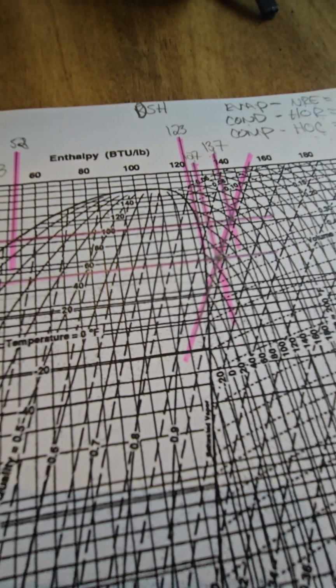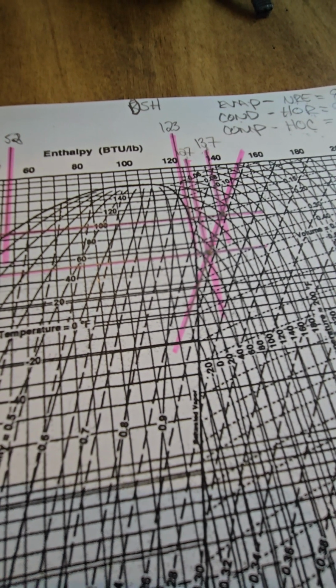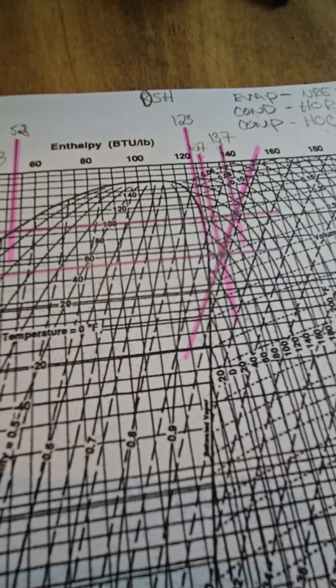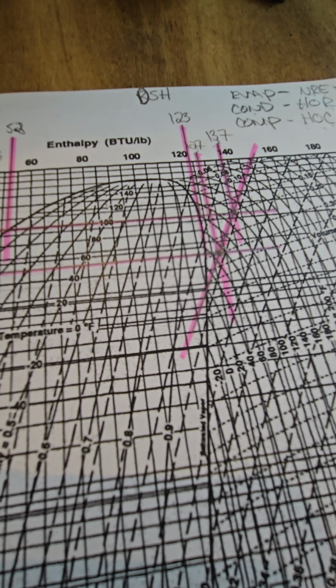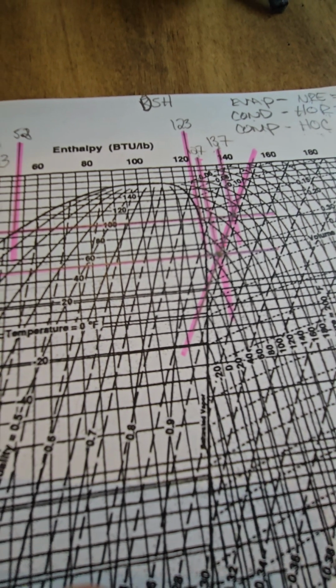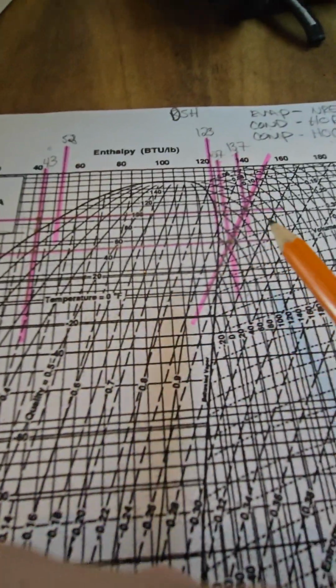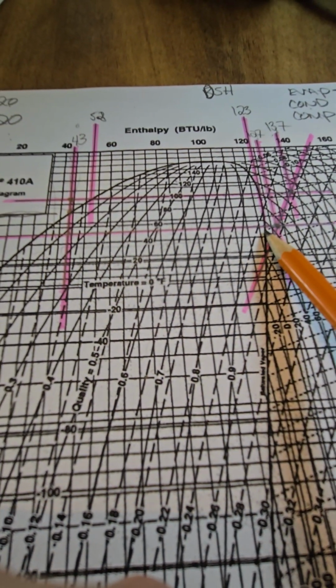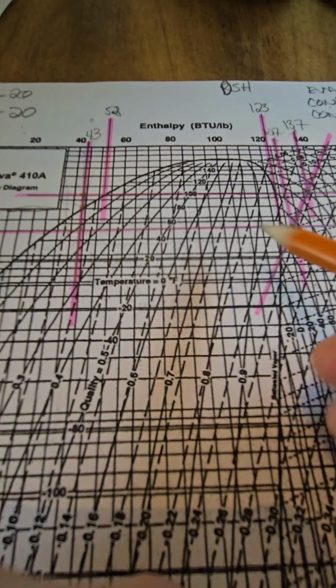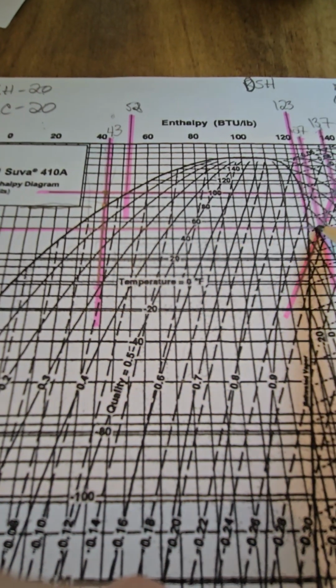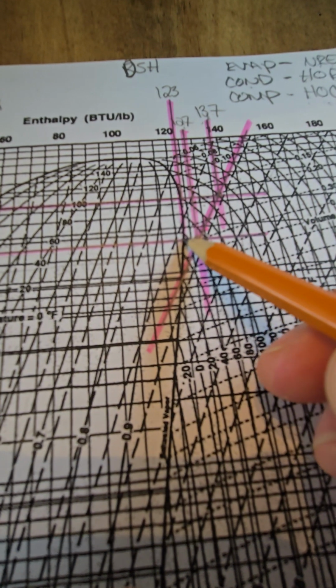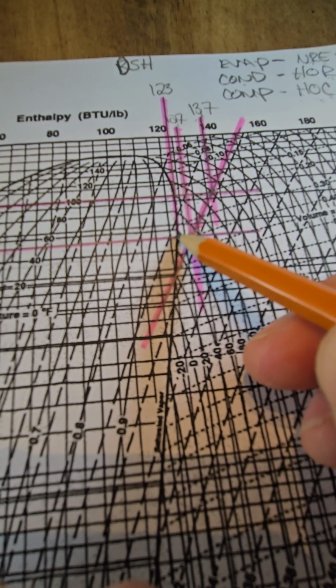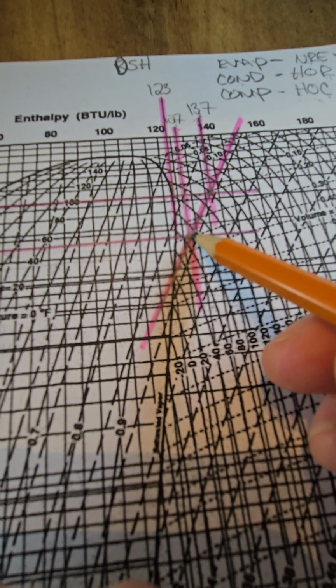Now, he might ask questions like, how many BTUs did it take to superheat the refrigerant? Superheating takes place in your evaporator, so you know it's going to be on this evaporator line. Superheat takes place after saturation, so you know it's not superheating here because it's a latent exchange. So from the minute it leaves saturation to the point of...